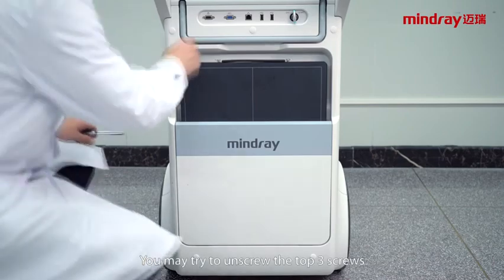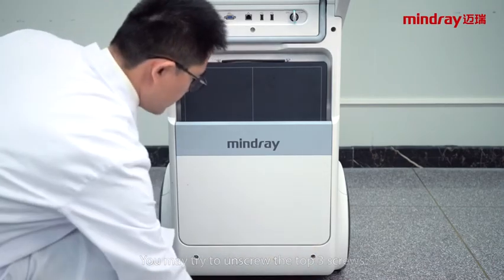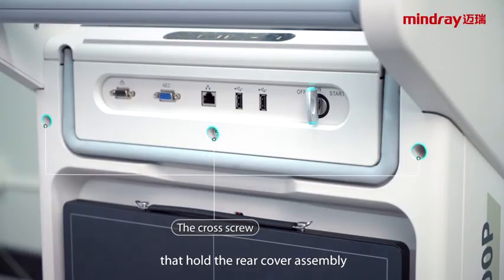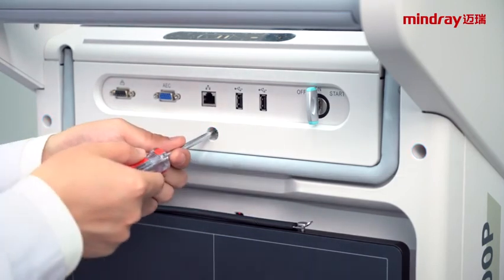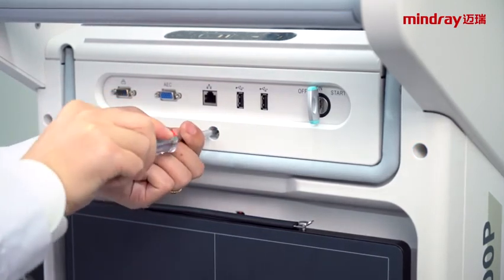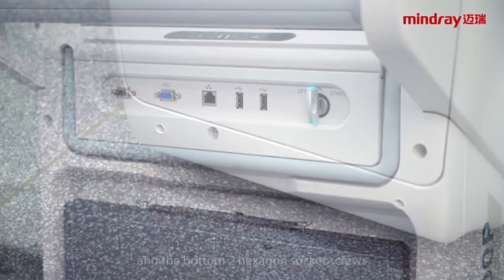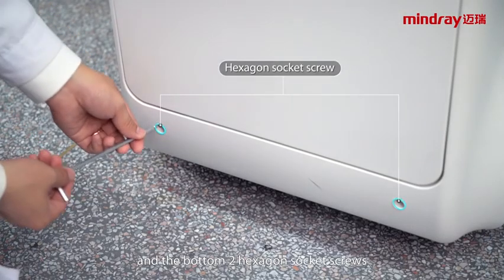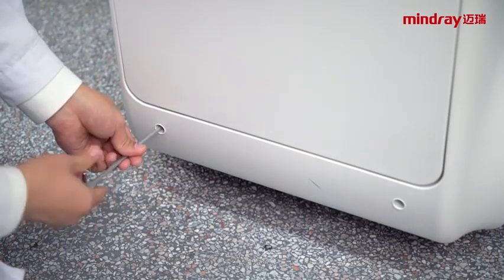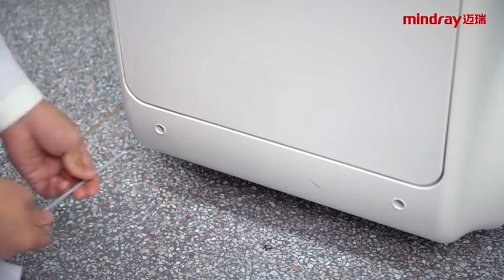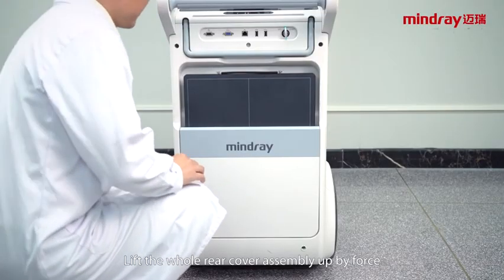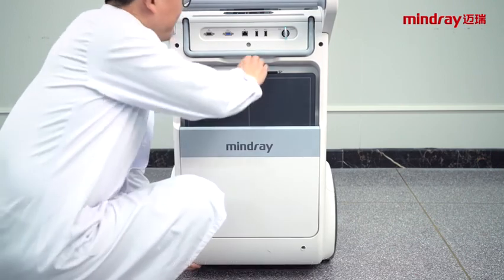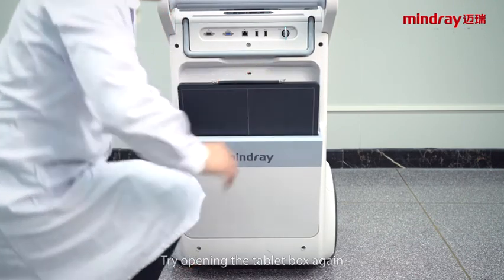You may try to unscrew the top 3 screws that hold the rear cover assembly, and the bottom 2 hexagon socket screws. Lift the whole rear cover assembly up by force. Try opening the detector box again.